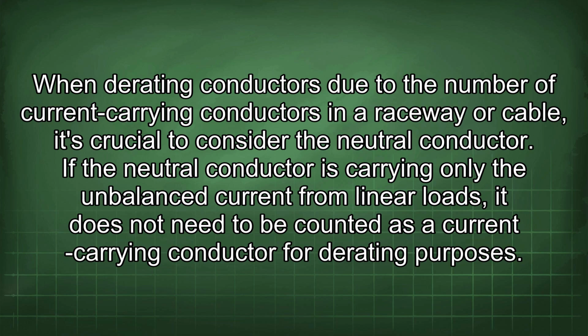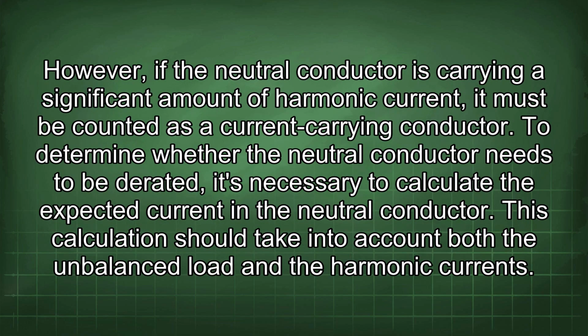If the neutral conductor is carrying only the unbalanced current from linear loads, it does not need to be counted as a current-carrying conductor for derating purposes. However, if the neutral conductor is carrying a significant amount of harmonic current, it must be counted as a current-carrying conductor. To determine whether the neutral conductor needs to be derated, it's necessary to calculate the expected current in the neutral conductor. This calculation should take into account both the unbalanced load and the harmonic currents.